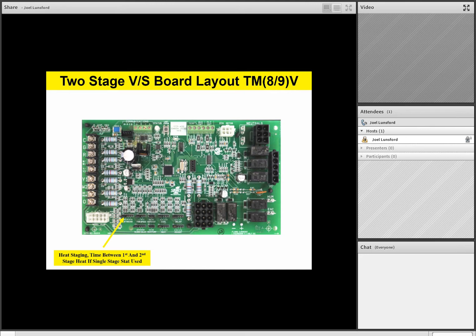Now this is very, very important. We ship that staging jumper in the off position. If you keep it in the off position and you have a single stage thermostat hooked up to the board, then when you get a W1, or first stage heating call, the board will never go out of first stage heating. It'll be stuck in first stage heating. So be sure, if you're stuck with a single stage thermostat, you put that jumper on 10, 15, or 20 minutes. Otherwise, you'll never go to second stage.